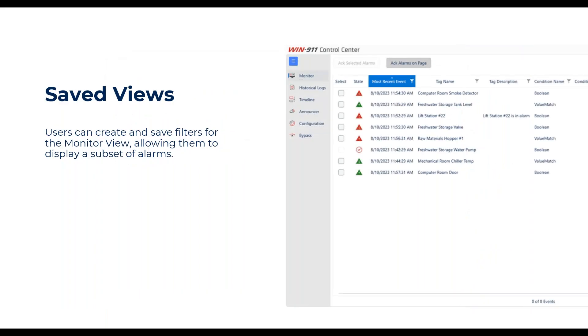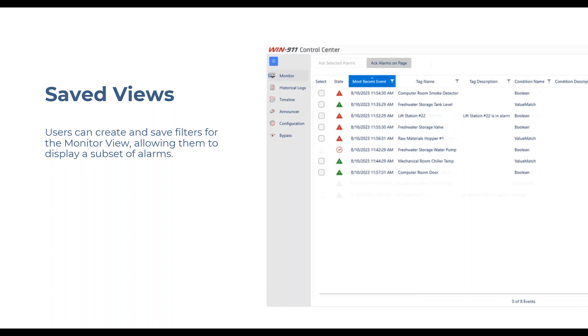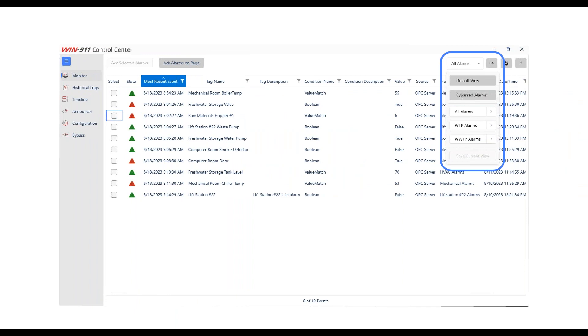Once you figure out what you want to show in your live monitor window, you can actually save that view. So if you set up filters on particular columns, turn columns on or off, and get it exactly the way you want, you can save that view and create several different views. You can view bypassed alarms, and if you're connecting to multiple systems, you can have different views set up for individual WIN-911 systems and easily switch between them in the top drop-down menu.